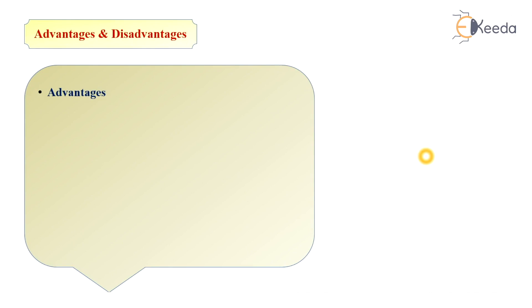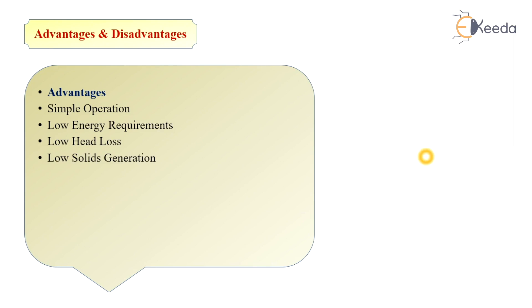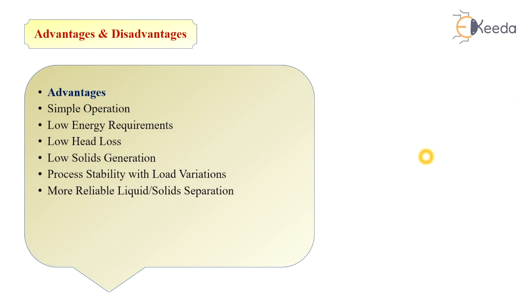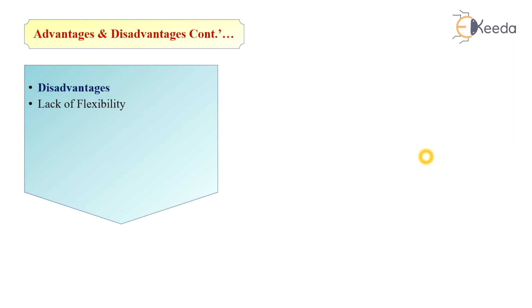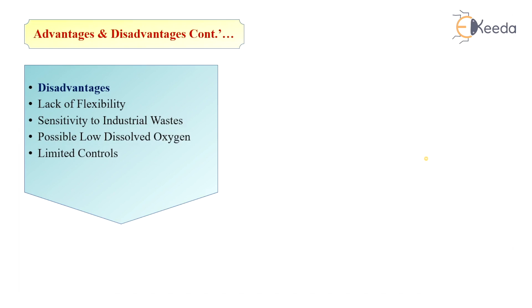Advantages and disadvantages of RBCs: Advantages include simple operation, very low energy requirement, low head loss, low solids generation, process stability with load variations, reliability for liquid-solid separation, no sludge return required, and high contact time with high effluent quality for both BOD and nutrients. Disadvantages include lack of flexibility, sensitivity to industrial waste, possible low dissolved oxygen, limited control over the process, and limited operator experience — proper training should be provided.